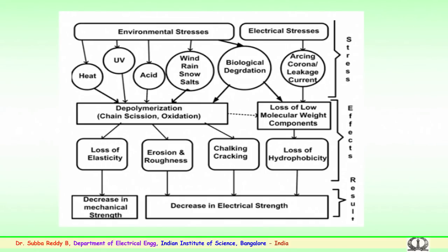This depolymerization could further lead to loss of elasticity, that is, the rubber could become brittle or stiff. This could again lead to mechanical issues, a decrease in the mechanical strength. Further, erosion or roughness of the material, or material peeling off from the surface because of continuous discharges or damages, and chalking or cracking because of the stiffness.